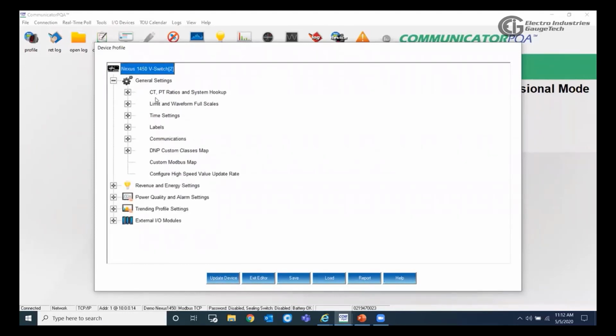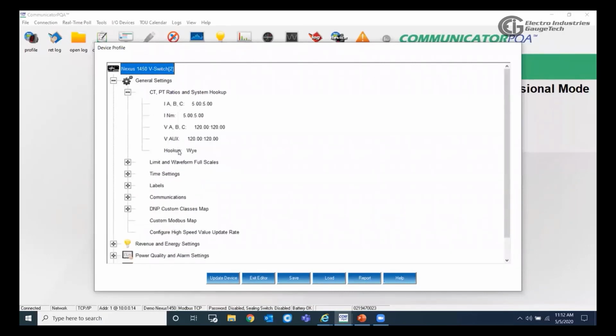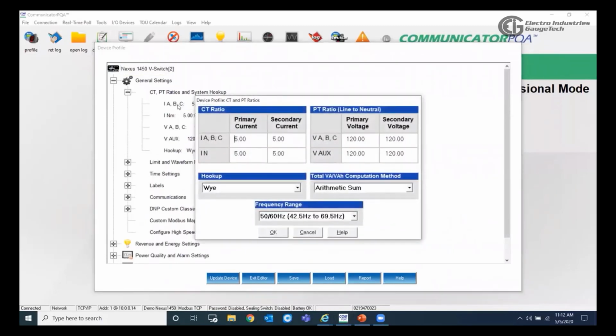Under the general settings, we have CT-PT ratios and system hookup. It's one window for all of these, so I can choose any of them. And this is where we set the CT ratio. So let's say that this meter would be installed in a panel or a switch gear using a CT size 800:5. So I would set the primary to 800 and the secondary to 5. And this meter also gives you the option to have a CT on the neutral current also. So if you have that, you can set it also here on IN.